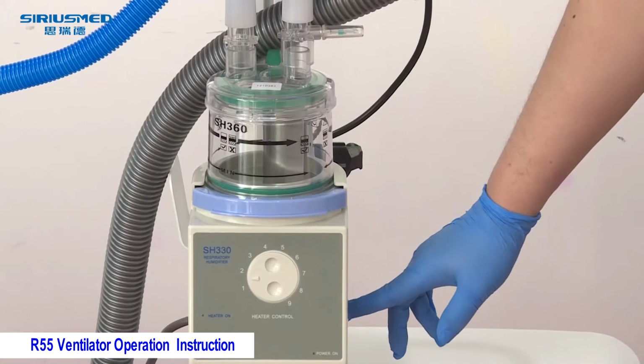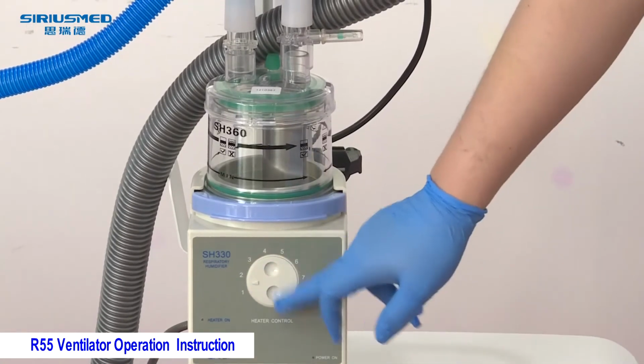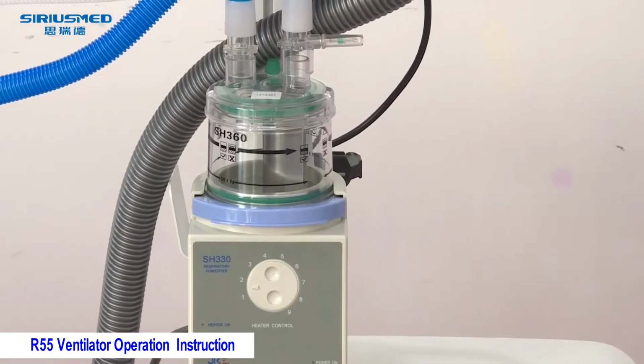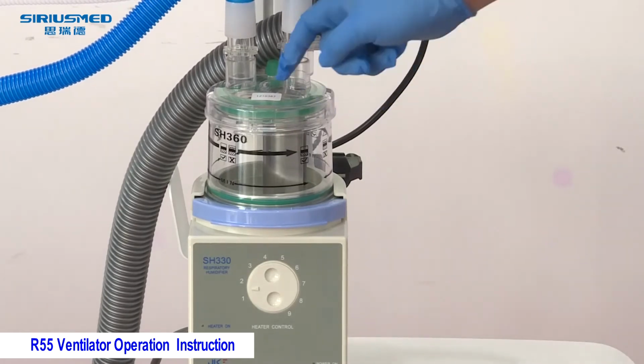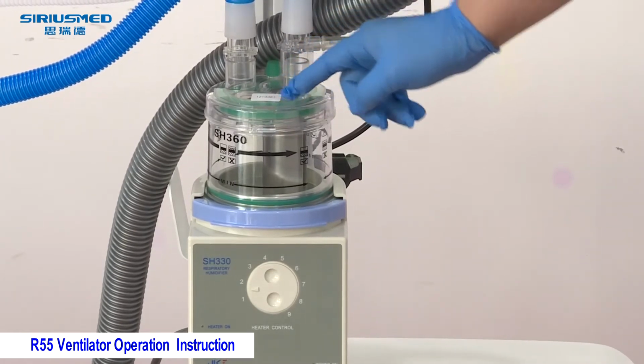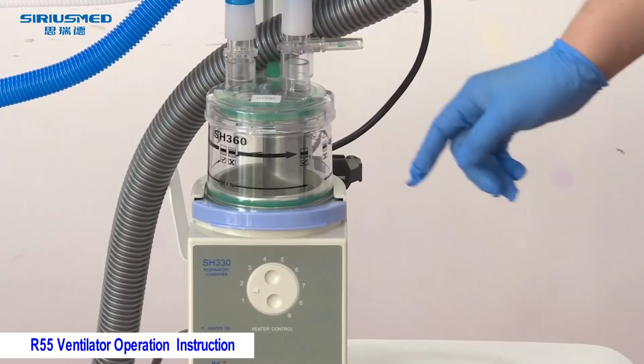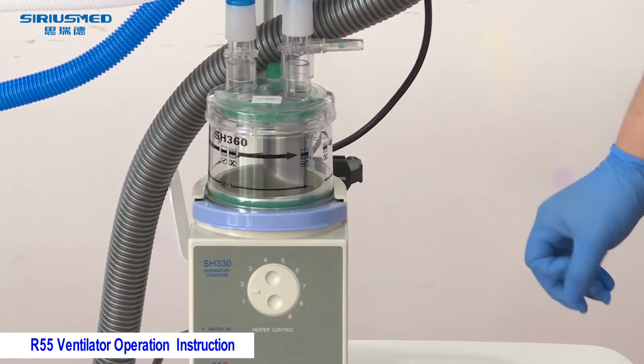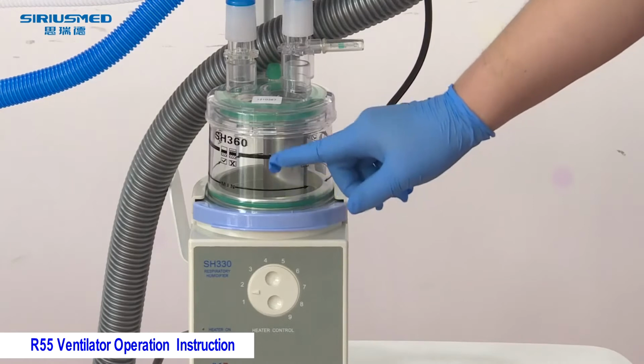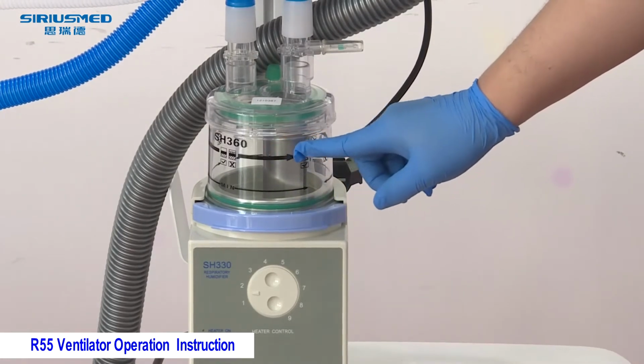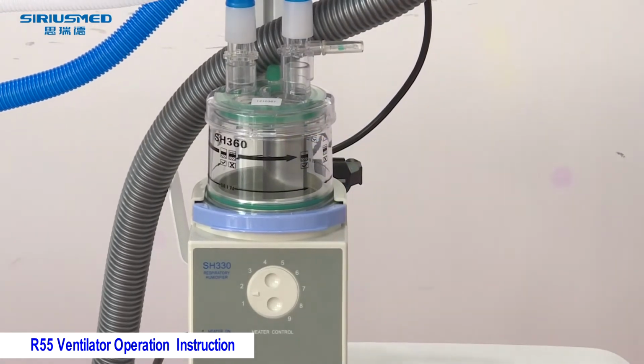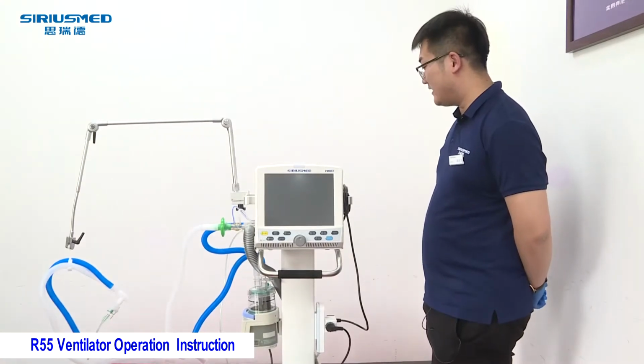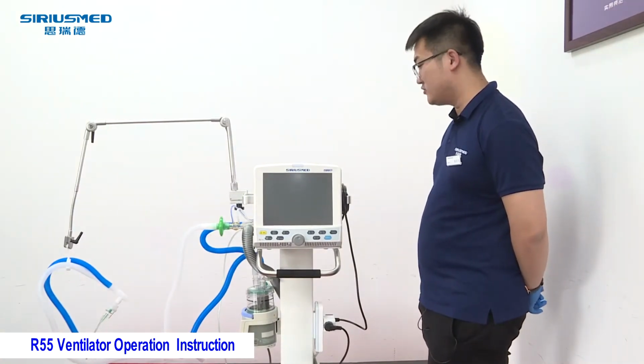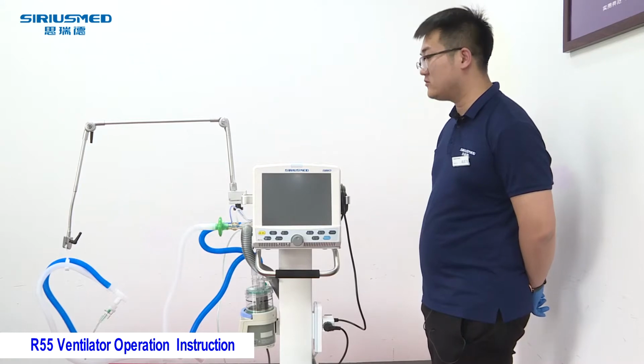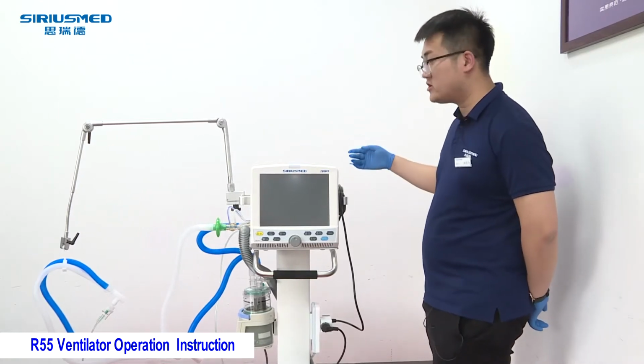Switch for the humidifier, and this one is to adjust the temperature. Pay attention, we need to put the distilled water first, and then we can connect the cable and adjust the temperature. And there is a minimum and maximum level for the distilled water. After we install all the circuit, we can use the machine. Firstly, we need to turn on the machine. The switch is in the back.